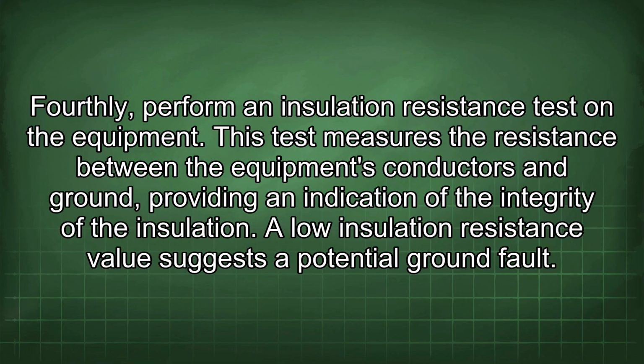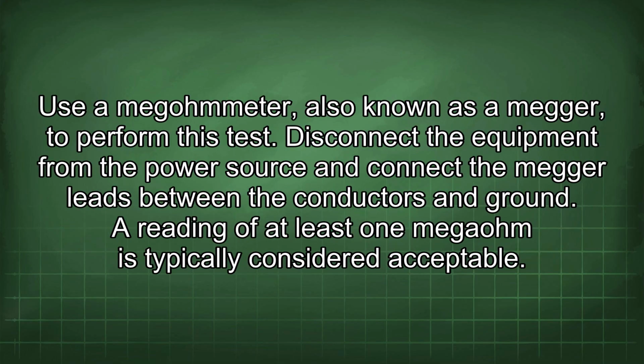Fourthly, perform an insulation resistance test on the equipment. This test measures the resistance between the equipment's conductors and ground, providing an indication of the integrity of the insulation. A low insulation resistance value suggests a potential ground fault. Use a megohmmeter, also known as a megger, to perform this test. Disconnect the equipment from the power source and connect the megger leads between the conductors and ground. A reading of at least 1 megohm is typically considered acceptable.